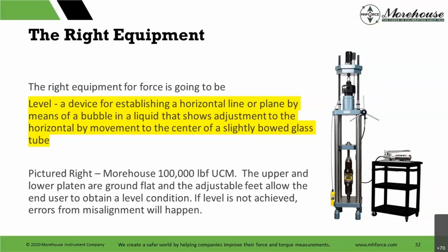The right equipment is going to be level, a device for establishing a horizontal line or plane by means of a bubble in a liquid that shows adjustment to the horizontal by movement of the center of a slightly bowed glass tube. You can measure this lots of ways. The more level you have the machine, the better. We have adjustments on the feet. You can use a machinist level, you can use all kinds of things, bubble levels. This load cell in the specification basically says, for 1/16 of an inch, the error is 0.0003. So if I'm off level a little bit, less than 1/16 of an inch, I know I could have an additional error source that I'm going to put in my budget.